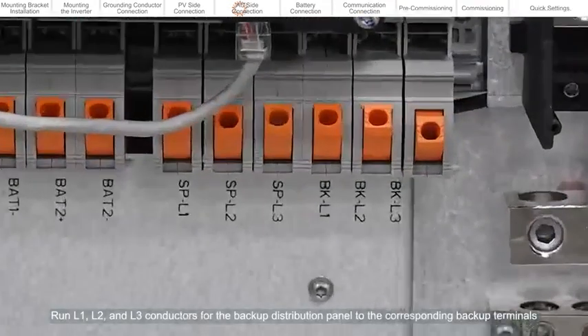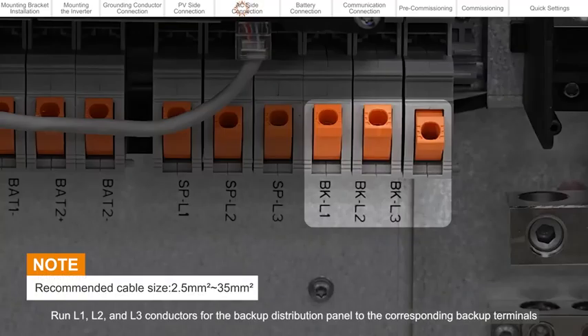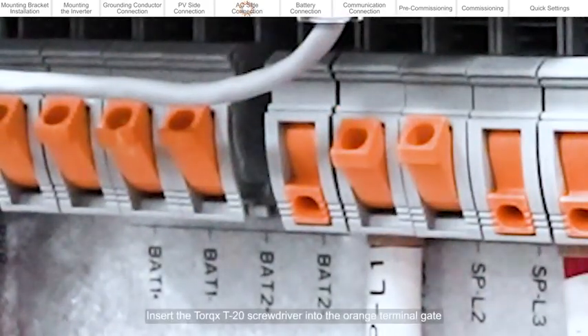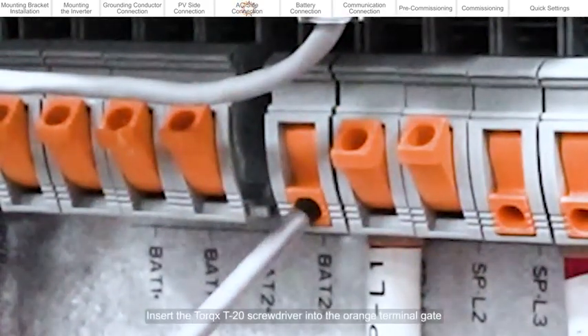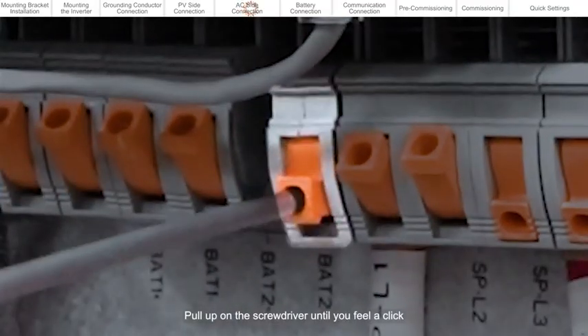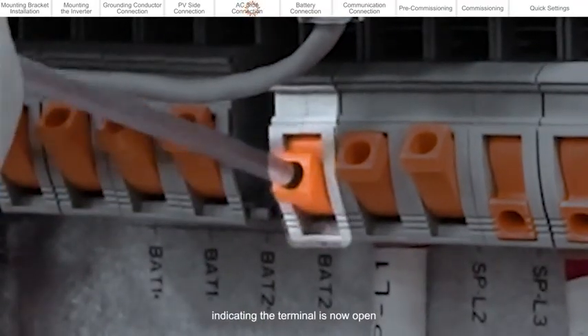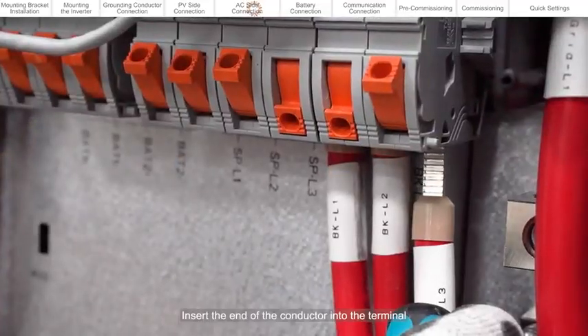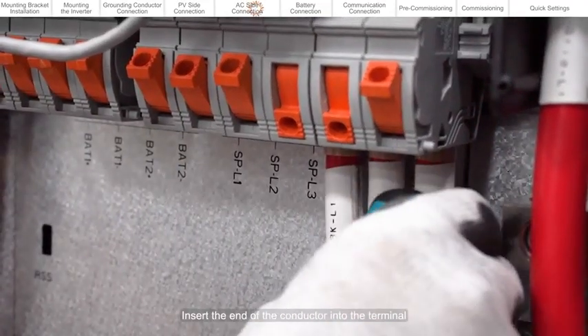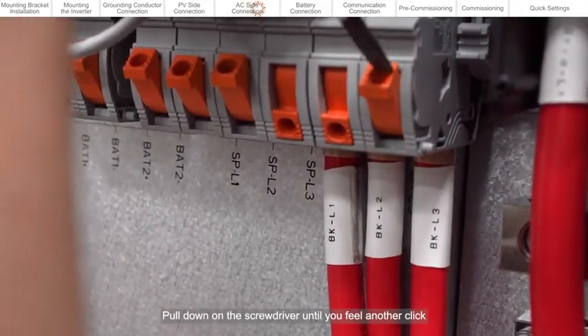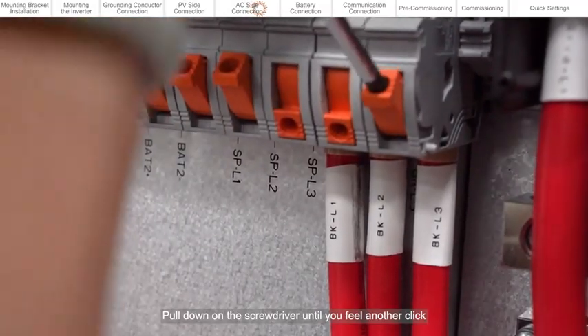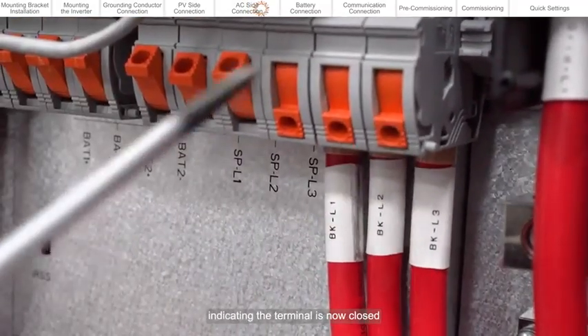Run L1, L2, and L3 conductors from the backup distribution panel to the corresponding backup terminals. Insert the Torx T20 screwdriver into the orange terminal gate. Pull up on the screwdriver until you feel a click, indicating the terminal is now open. Insert the end of the conductor into the terminal. Pull down on the screwdriver until you feel another click, indicating the terminal is now closed.